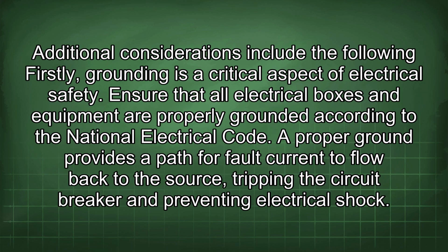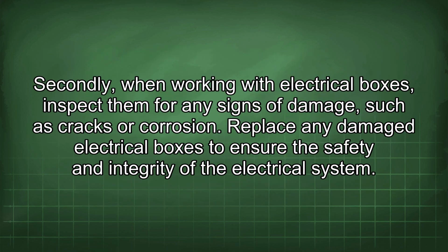Additional considerations include the following. Firstly, grounding is a critical aspect of electrical safety. Ensure that all electrical boxes and equipment are properly grounded according to the National Electrical Code. A proper ground provides a path for fault current to flow back to the source, tripping the circuit breaker and preventing electrical shock. Secondly, when working with electrical boxes, inspect them for any signs of damage, such as cracks or corrosion. Replace any damaged electrical boxes to ensure the safety and integrity of the electrical system.